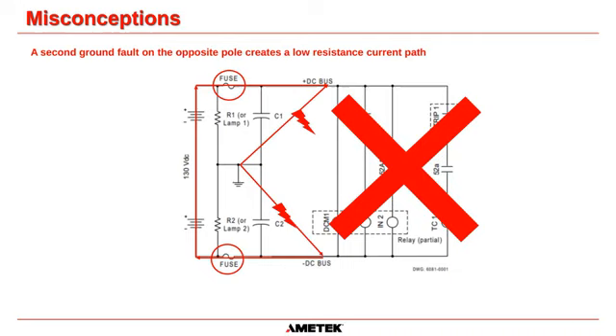Okay, so another question on the capacitors. Based on your explanation of capacitor construction inside a charger, may we say the internal failures to a charger are more common to the negative to ground than positive to ground? In my experience, absolutely. But once again, that is my experience, because the capacitor manufacturers tend not to have the positive of the can connected to ground. There are other things, like I said, within a charger, it can be insulation wear on a cable, and that can be on either positive or negative. It could be that there is a loose connection, and that loose connection has come apart and is touching the ground, and that could be on positive and negative. But in my experience, in the 20 odd years that I've been working on DC systems, if it's in the charger, it tends to be a negative ground fault.